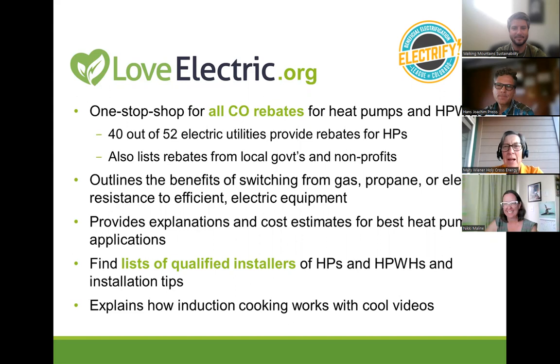Yeah. The next question we already answered is what the supplemental heat would be in an electric home. So if you're doing the air to water, he talked about that electric kind of boiler system. Ductless heat pumps, a lot of people keep their electric baseboard heat in. And then with a ducted furnace, you can add a 5 kilowatt, which is 5,000 watt, or 10 kilowatt electric resistance backup on that air handler. So those are kind of most of your options, right? Exactly. Electric strip heater in an air handler can be done.